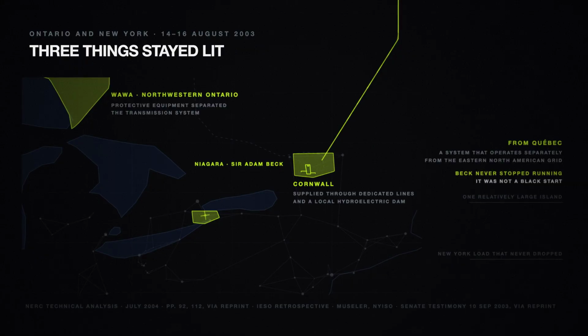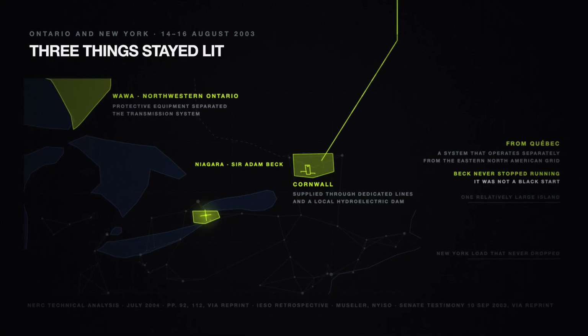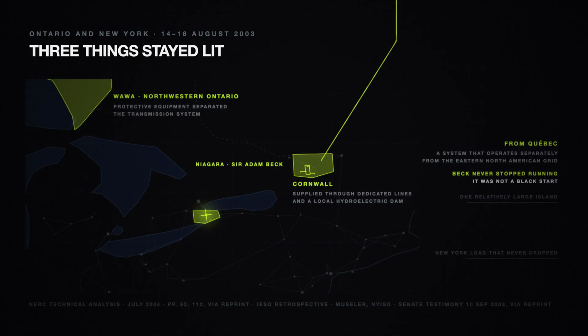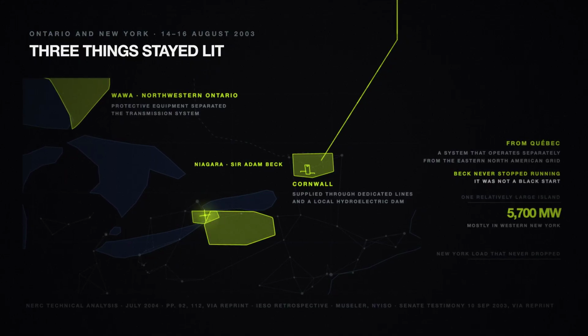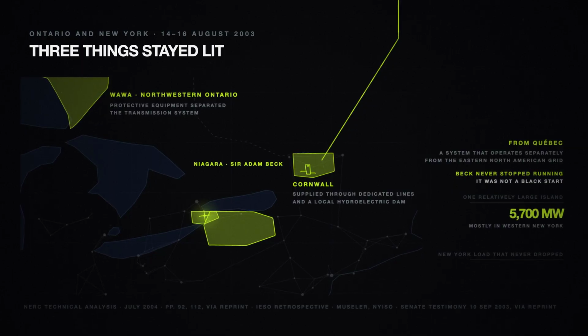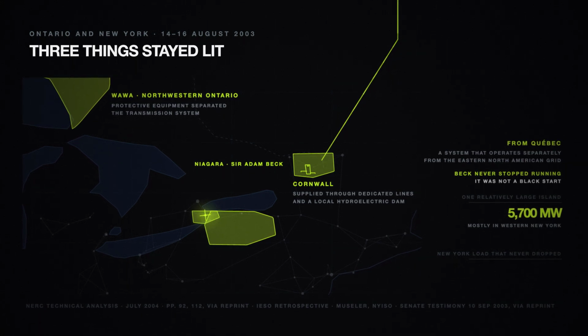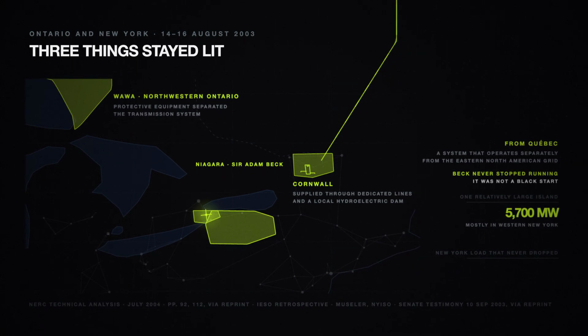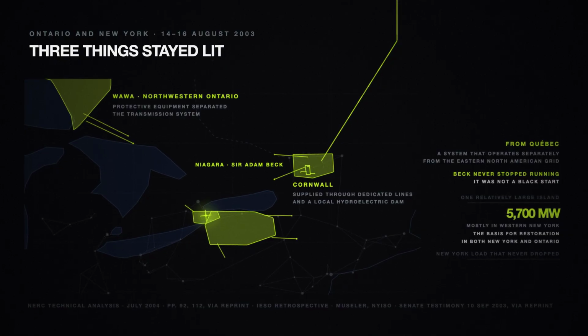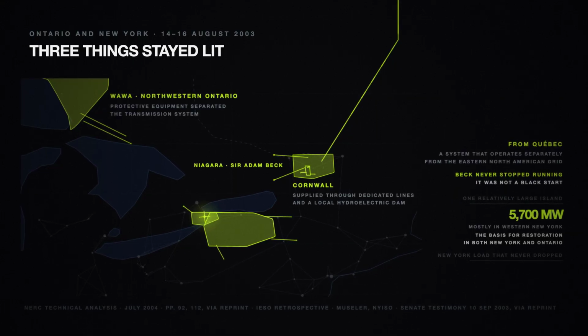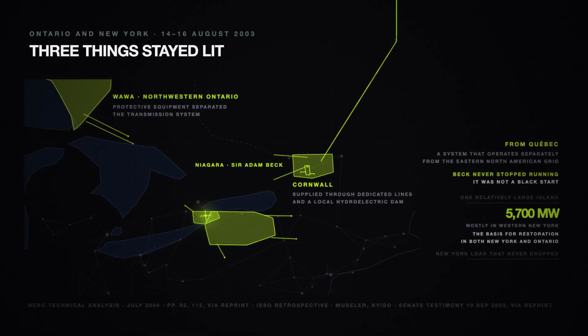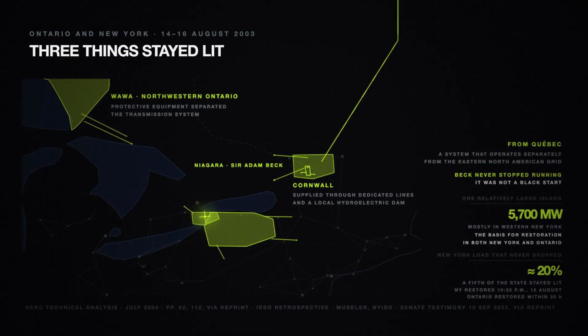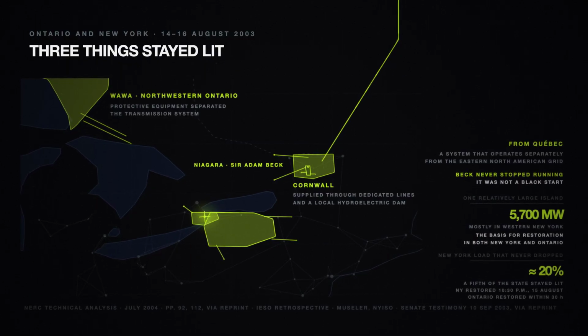Read that last one precisely because it is usually told backwards. Beck did not black start the system. Beck never stopped running. South of the border, the same thing happened, larger. One relatively large island remained in operation, serving about 5,700 megawatts of demand, mostly in western New York. That island, the reliability organization's own analysis says, formed the basis for restoration in both New York and Ontario. About 20% of New York's load never dropped at all. A fifth of the state stayed lit, and that fifth is what the rest was rebuilt from, over about 30 hours.